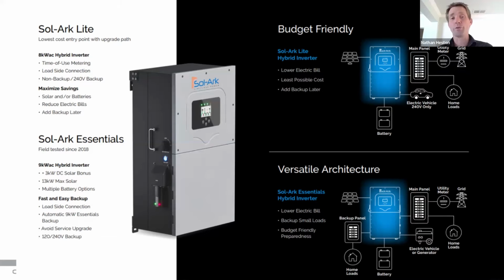Absolutely agree on DC coupling. And I would say on the generator side of things, oftentimes when your generator comes on, you're also charging batteries as well as supporting loads. So if you reduce that charge rate of your batteries from pulling on the generator, you might not need such a big generator. You mentioned needing a 22 kilowatt generator just to stay on. But you can do some clever things with a Sol-Ark to limit that.